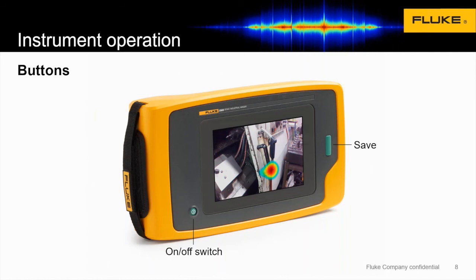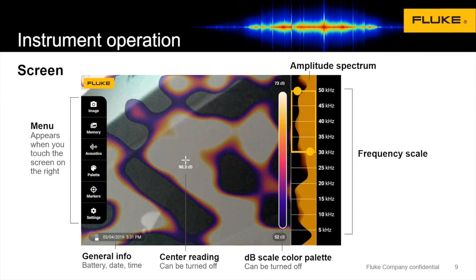Let's talk about the operation of the unit. There are two hard buttons: you've got the opportunity to save an image or a video, and then an on/off switch. The rest of the operation is through the touch screen. When you turn on the camera, you've got menu options on the left. If you select Image, that allows you to switch between images, videos, or what's called leak quantification. The Memory button takes you to a library of all the images stored on the device. The Acoustics menu allows you to make adjustments to the decibel levels you're picking up and fine-tune the unit for your specific applications.